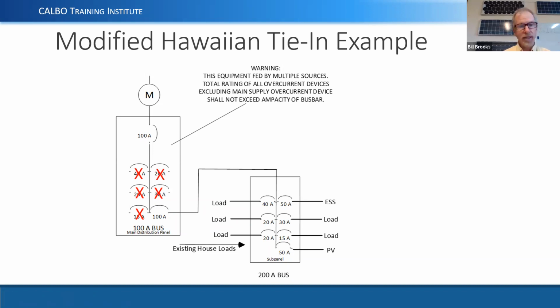And we haven't violated a single thing in the code, and all the excess power can come back up through here. And because we've used the sum of the breakers and not the 120% rule, we can feed back 100 amps back through that panel up to the grid. So very, very important point. A lot of people don't know this yet, but hopefully catch on to this. Saves you a lot of time and money. A 200 amp main lug panel is an inexpensive device. There is some wiring involved, but if we're talking about energy storage, there's almost always some wiring involved. A lot of folks want to be able to just walk in and put in a whole house backup system and do it in a couple hours, it's going to take more than a couple hours. It usually takes a day or two, at least.